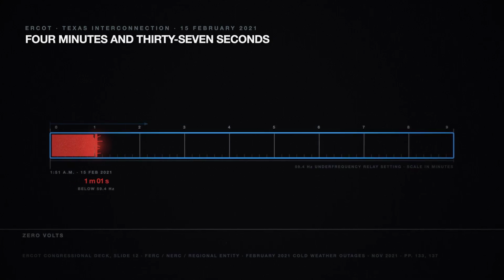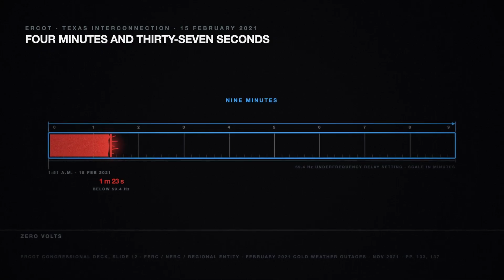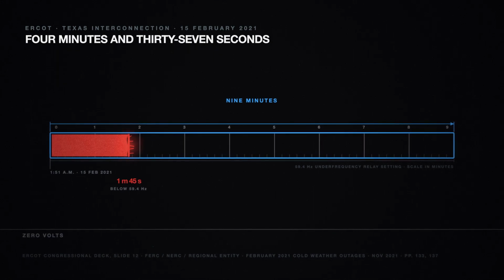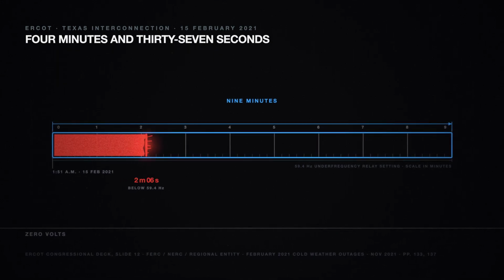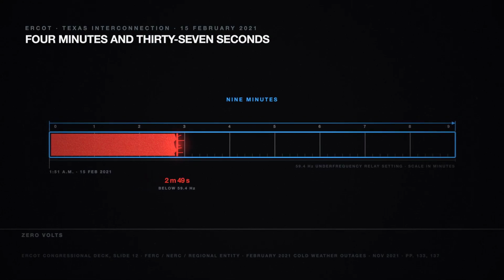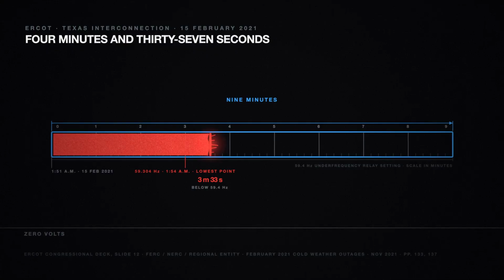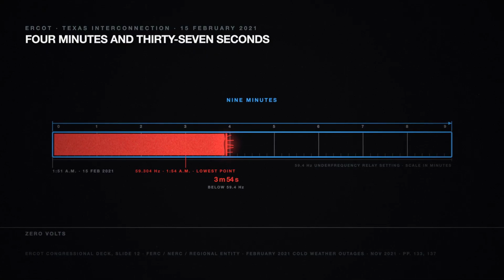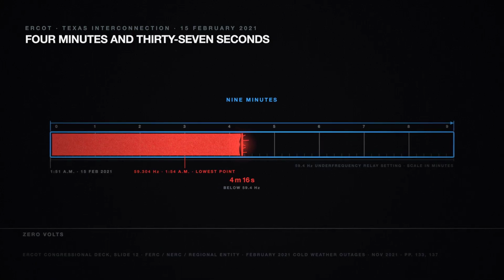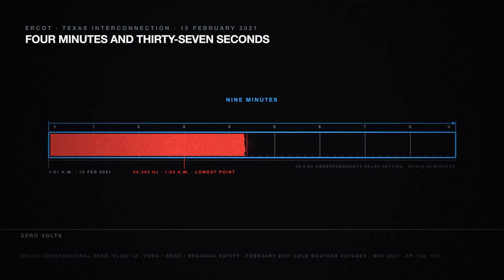February 2021, Winter Storm Uri. At 1:51 in the morning on the 15th, frequency on the Texas grid fell below 59.4 Hz. That number is a relay setting. Below it, generator under frequency relays start a 9-minute timer. If frequency is still under the threshold when it runs out, those generators disconnect to protect their own machinery. Frequency stayed below 59.4 Hz for 4 minutes and 37 seconds. Its lowest point was 59.304 Hz at 1:54. Then it recovered and the timers reset.